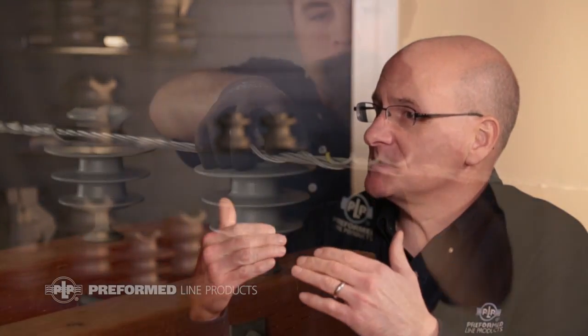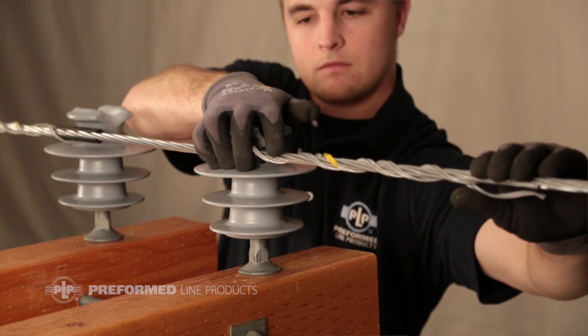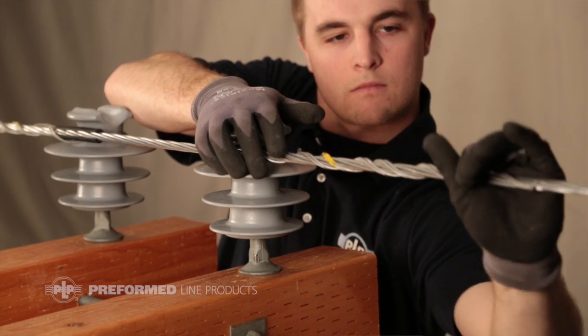They will withstand droppage and will also provide better ballistic protection — the insulator can stay intact if shot with a gun. It has high mechanical strength, so we can meet those unbalanced loads as well as vertical pull-off requirements that the system has. Polyethylene has a low coefficient of friction. By having a low coefficient of friction, we can reduce or eliminate abrasion damage to the conductor. And finally, the material we use is very environmentally friendly and has a high environmental integrity.